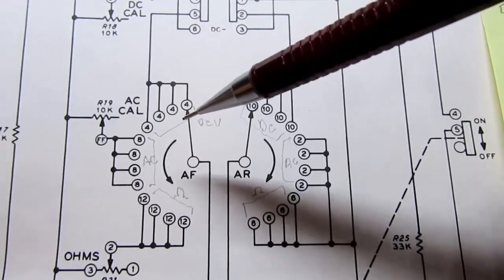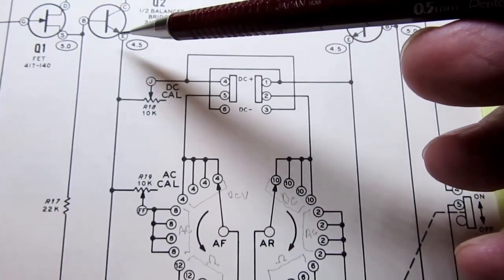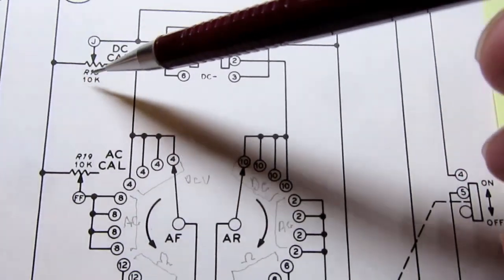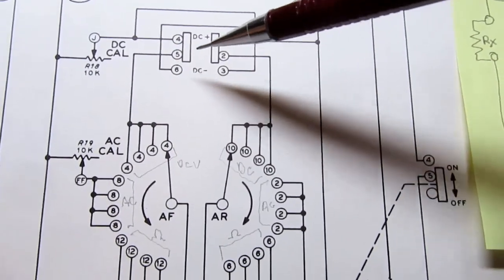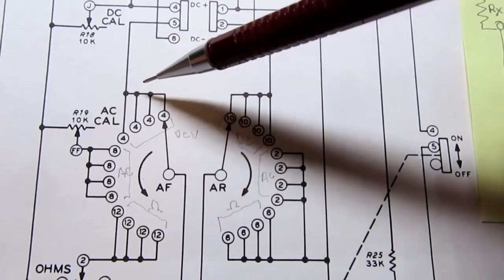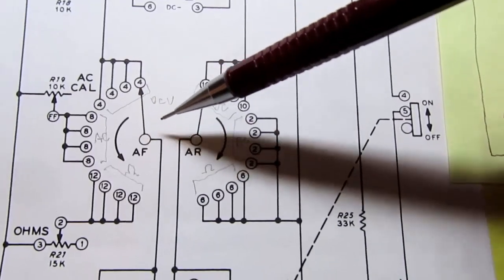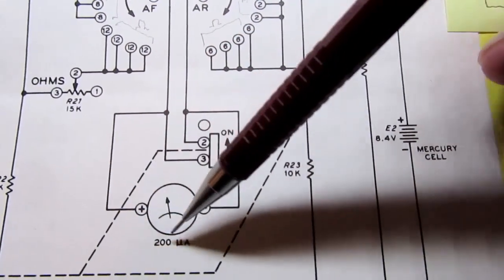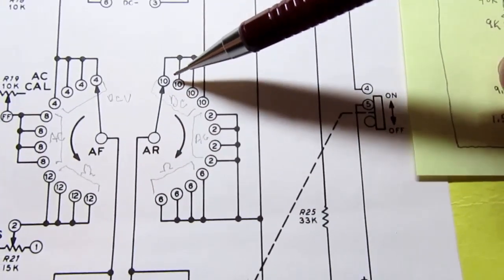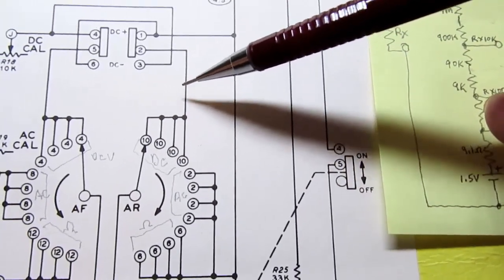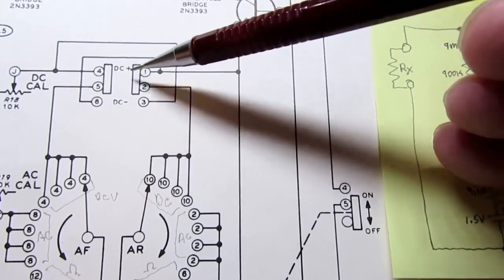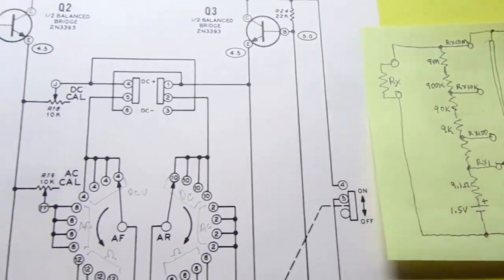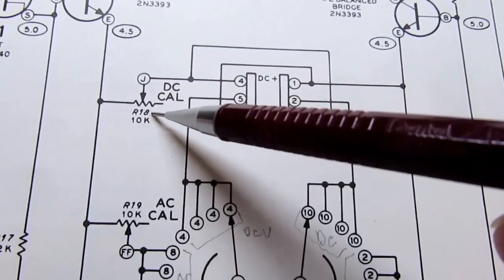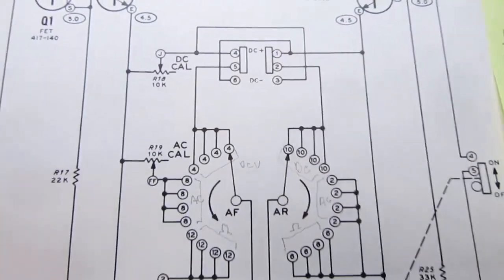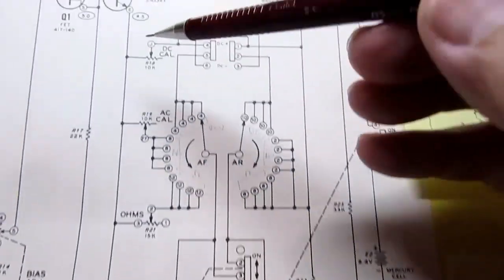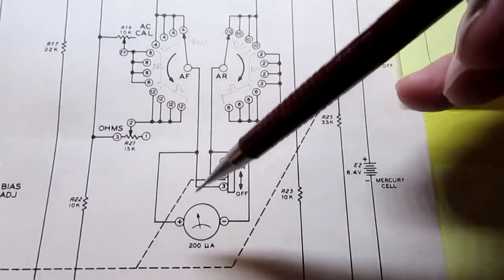So when the meter is selected to DC volts, then you've got voltage here and it's trying to drive current through a 10K resistor and then through the DC plus and minus switch, and then down through here, through one of these DC positions on the function switch, down here through the meter movement, back out of the meter movement, come up here, go through one of these positions on the function switch, back through this DC plus and minus switch, and to the right-hand rail of the meter driver. So that's the path, and by adjusting this 10K DC cal pot, you can adjust exactly how much meter deflection you get for a given voltage difference, and that allows you to calibrate the DC volts.